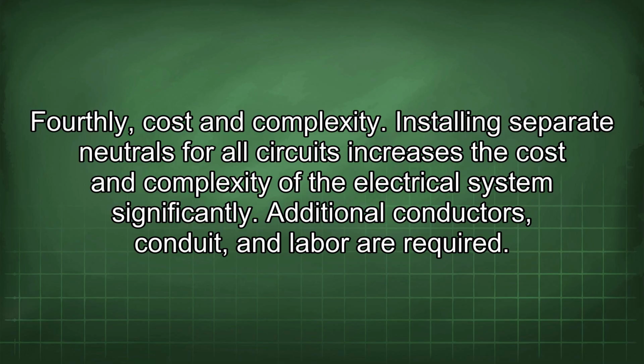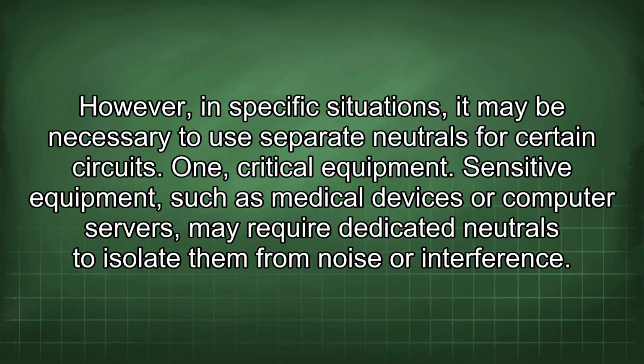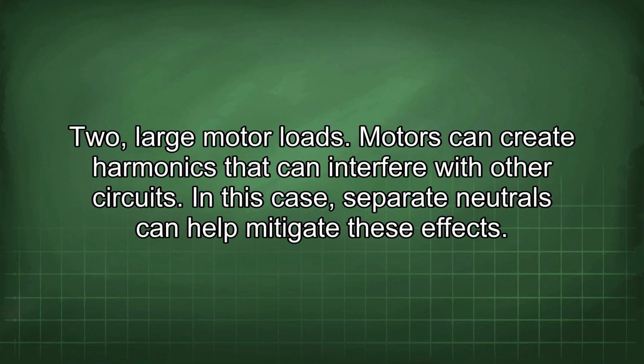Fourthly, cost and complexity. Installing separate neutrals for all circuits increases the cost and complexity of the electrical system significantly. Additional conductors, conduit, and labor are required. However, in specific situations, it may be necessary to use separate neutrals for certain circuits. 1. Critical equipment. Sensitive equipment, such as medical devices or computer servers, may require dedicated neutrals to isolate them from noise or interference. 2. Large motor loads. Motors can create harmonics that can interfere with other circuits.